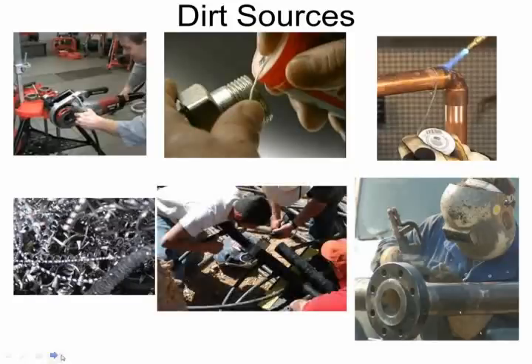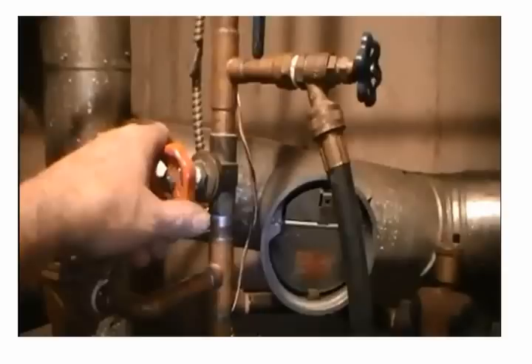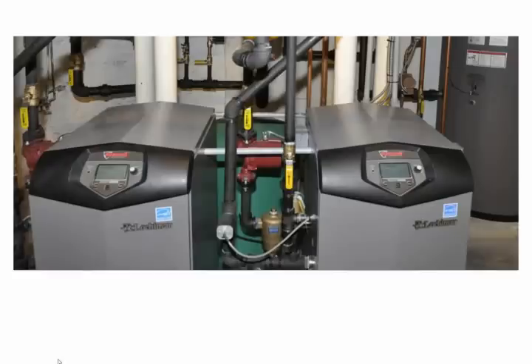But even real dirt could be an issue. Here's a shot from Santa Fe. This is actually dirt. These contractors are fusion welding some geothermal pipes, creating a manifold on that geo system. And if you've been out to geothermal sites such as this, you know they can get dirty and muddy, and the chances of dirt getting into your system are very high. Now, does the designer have to be very concerned about this? Well, not necessarily. They need to be knowledgeable, because the process of commissioning a system entails purging and filling the system so that any debris largely gets rinsed out of the system. But not all the time.